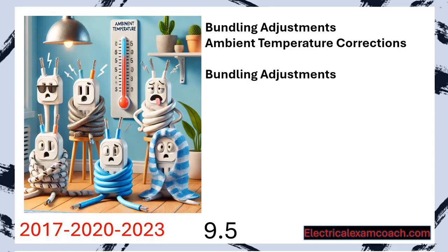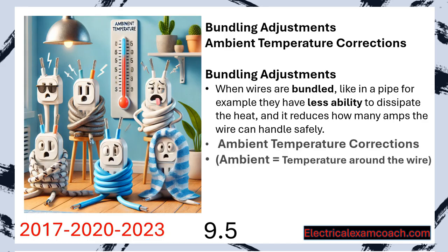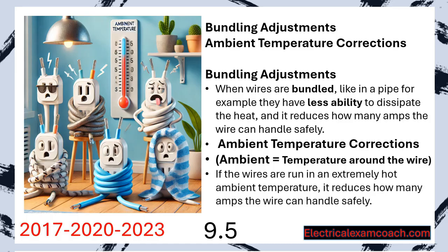Bundling adjustments work like this: when wires are bundled, like in a pipe for example, they have less ability to dissipate the heat, and it reduces how many amps the wire can handle safely. Ambient temperature corrections are like this: if wires are run in an extremely hot ambient temperature, it reduces how many amps the wire can handle safely. We're going to learn about these one at a time.